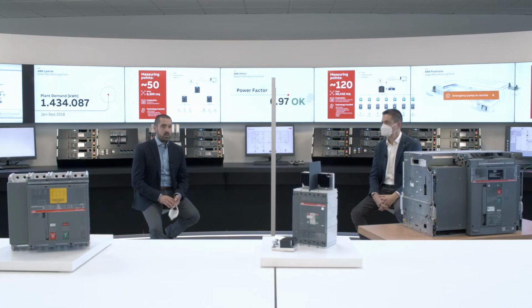The motor control unit can be mounted on the device and allows the customer to manage the operation of the product remotely. It is possible to supply the motor control unit with a wide range of supply voltages. Moreover, it is possible to find a wide range in the ABB catalog in order to complete the configuration of the product, like, for example, mechanical accessories like handles or different kinds of auxiliaries and other electrical accessories. It is also possible for the customer to choose between different kinds of installation. For example, it is possible to mount the small frames up to 250 amps directly on a DIN rail, or to have a fixed solution on a plate, or to choose between wireable or plug-in versions that make the maintenance of the installation easy. Thanks to this wide range of accessories, it is possible for ABB to cover all installation applications and to give the customer great flexibility.